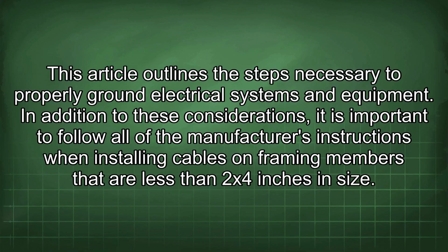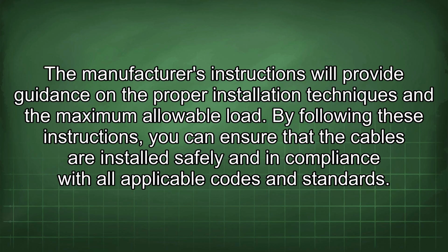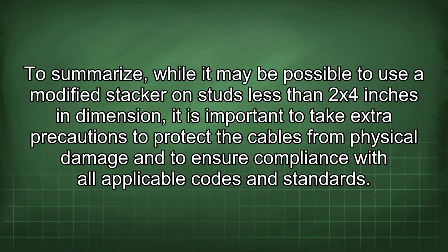In addition to these considerations, it is important to follow all of the manufacturer's instructions when installing cables on framing members that are less than 2x4 inches in size. The manufacturer's instructions will provide guidance on the proper installation techniques and the maximum allowable load. By following these instructions, you can ensure that the cables are installed safely and in compliance with all applicable codes and standards. To summarize, while it may be possible to use a modified stacker on studs less than 2x4 inches in dimension, it is important to take extra precautions to protect the cables from physical damage and to ensure compliance with all applicable codes and standards.